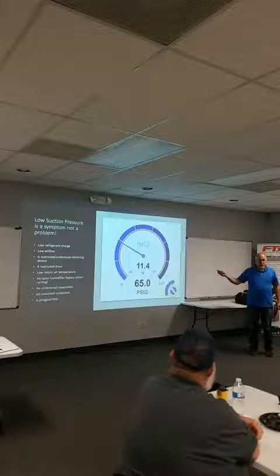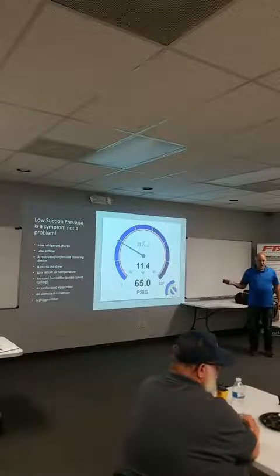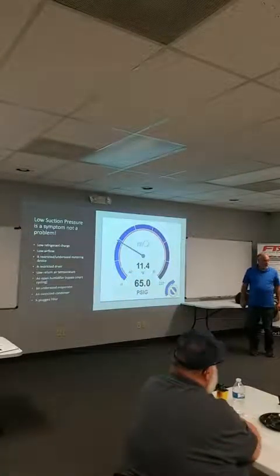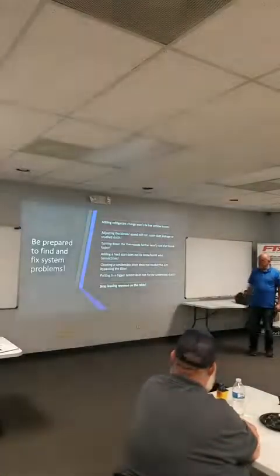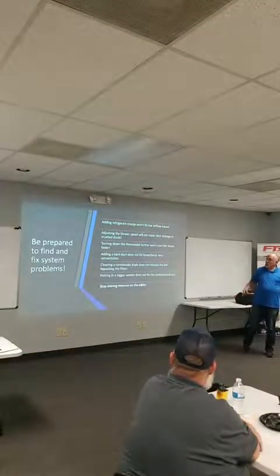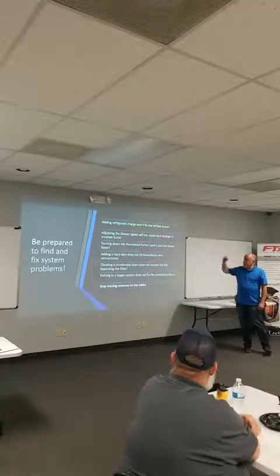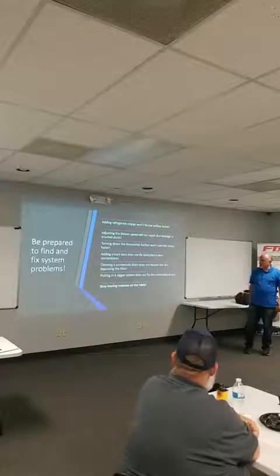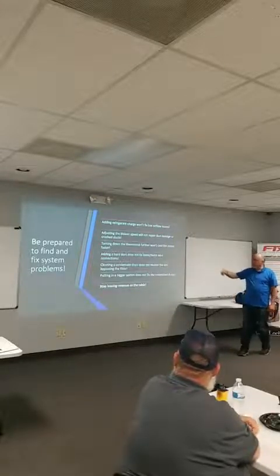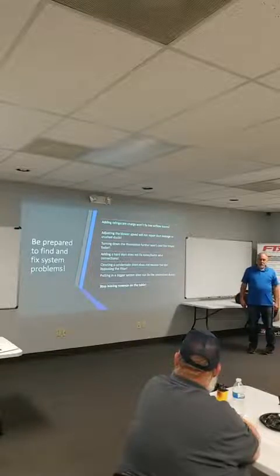So you gotta understand, when you see this low suction pressure on the machine, there should be a flag that there's something wrong. You don't obviously fix this by adding gas. Put gas in it, yeah, that's what this thing is, right? So, you know, adding charge is not gonna fix low airflow issues, adjusting blower speeds is not gonna repair crushed ducts, turning up the thermostat is not gonna cool it any faster. You know, I always see guys adding hard start components to the system.